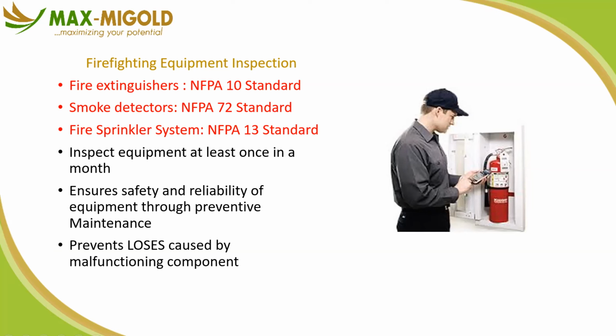If you have a 50 kg DCP - dry chemical powder - cylinder, let's use 25 kg for ease of math. If you have a 25 kg dry chemical powder cylinder on wheels in your generator house, the reliability of that 25 kg is embedded in itself because it only has one operating control. That means if there's a problem with that control, the whole 25 kg unit is as good as useless.